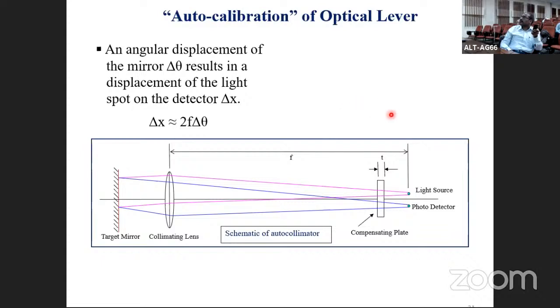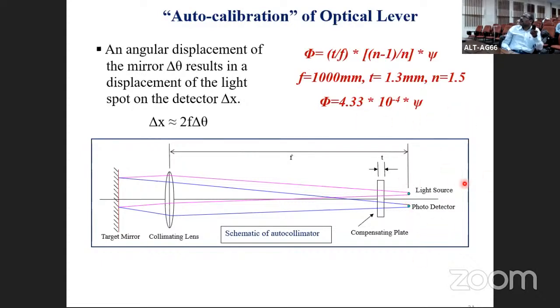So there is a formula here, and phi is the angle which you want to move of the compensating plate. These are the parameters of the formula: F is the focal length, T is the thickness of the glass plate, and N is the refractive index of the glass. And psi is the angle by which you push the compensating plate. So you use an encoder micrometer, and that is able to generate rotation at the arc-second level. So eventually you can get this angle as small as a few nanoradians. So you have to translate this compensating plate in the nanoradian region.